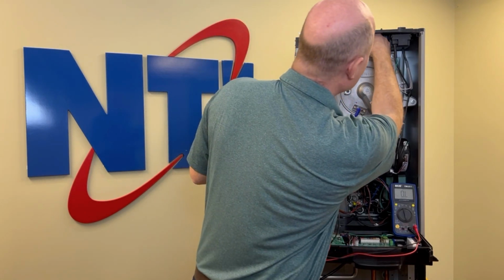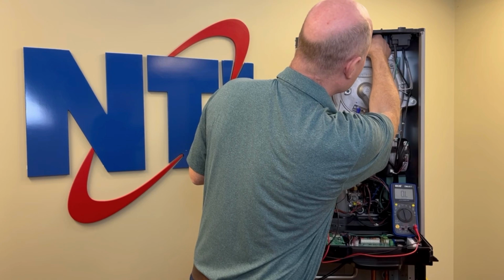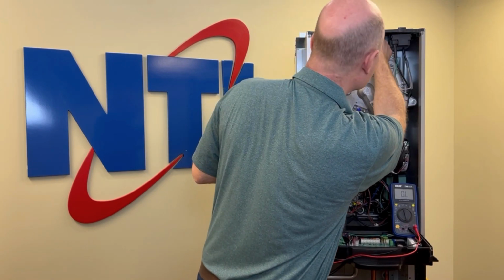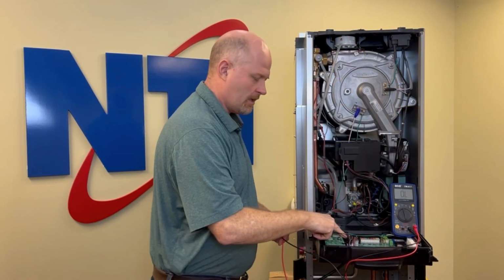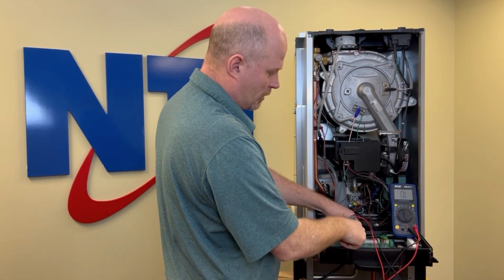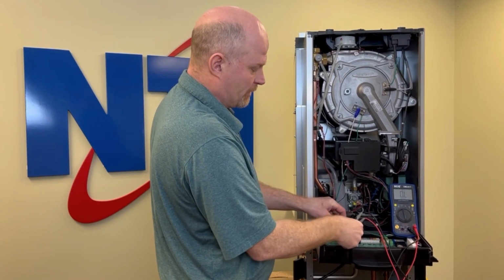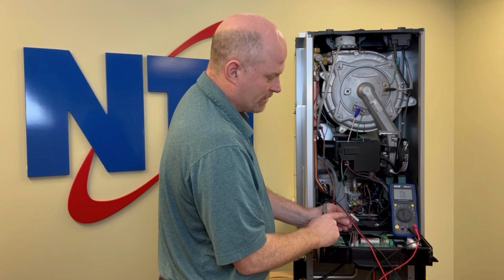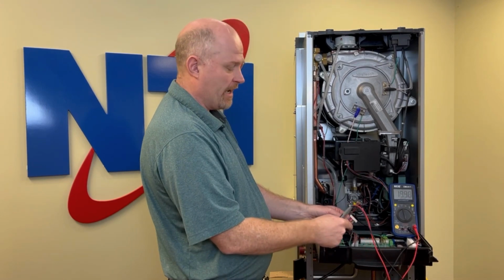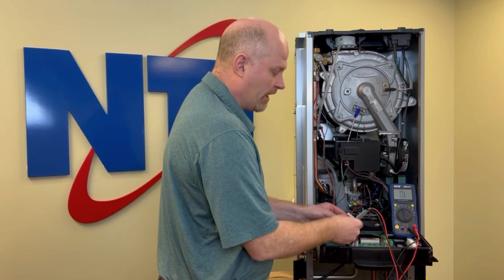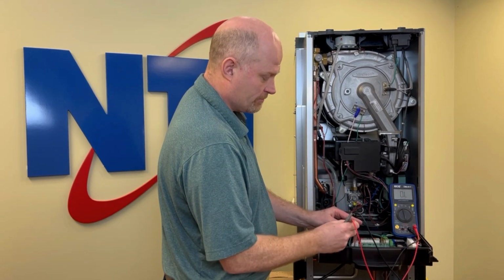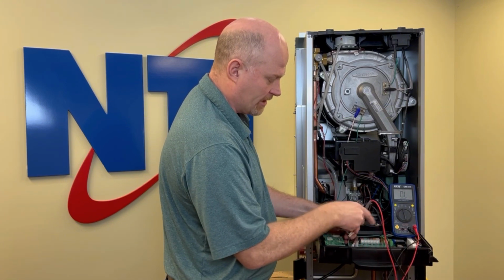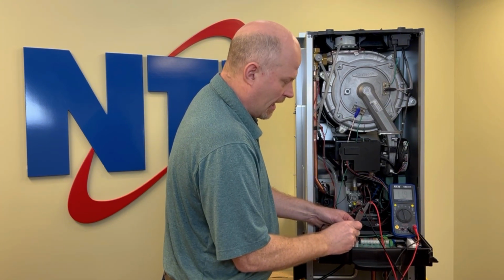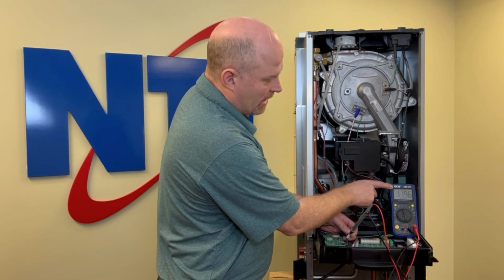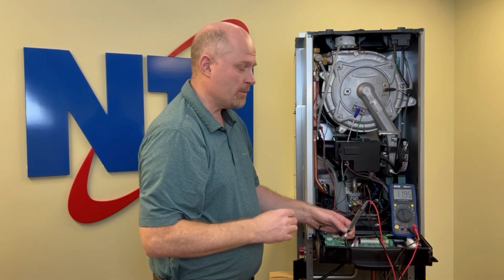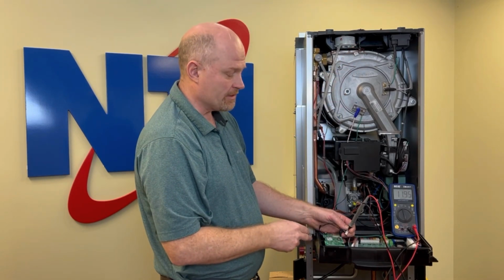The next thing would be to plug this sensor back in, come down to the main circuit board on the bottom left-hand corner, and remove the plug that is closest to the rear of the boiler. You'll know which one you're looking at because it has two blues, two reds, two browns, two grays, and it could have two or four black wires. The two you're concerned with are the two brown wires. To test this, stick one meter lead in each side of the connection and measure the reading that you get. If you get something other than the same reading you had up top, that would indicate that the wires are damaged or shorted in some way.